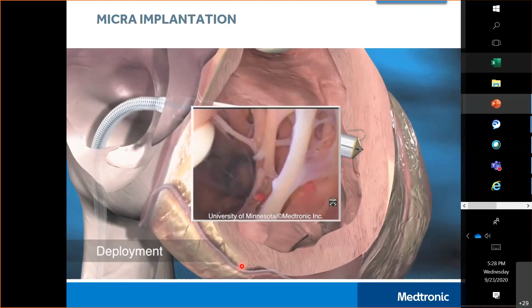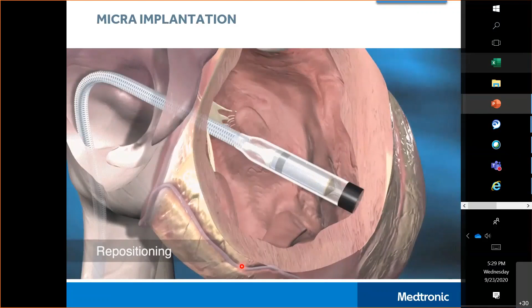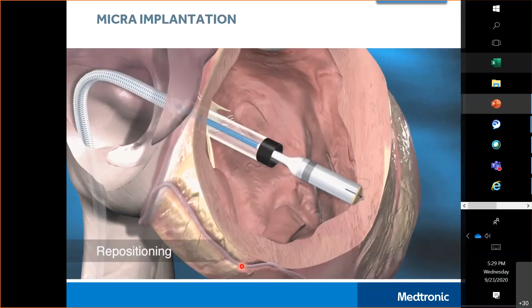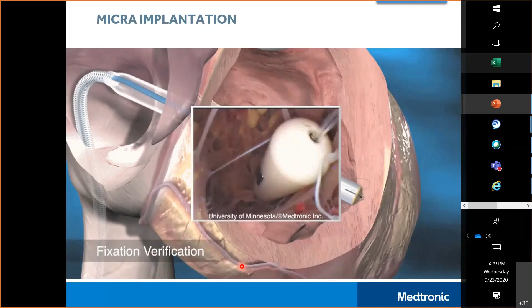So imagine where they place it in the heart the first time, it's the wrong spot. It won't do a good job of pacing the heart. So you need to recapture it. When you recapture it, you don't want to tear the heart muscle. And that put an upper spec limit of 3 newtons on the fixation force. Now you reposition it in a spot where it will do a good job of pacing the heart, and you want it to stay there forever. So now you do a little fixation verification, to make sure it's going to stay there for years, and that put a lower spec limit of 2 newtons of fixation force.